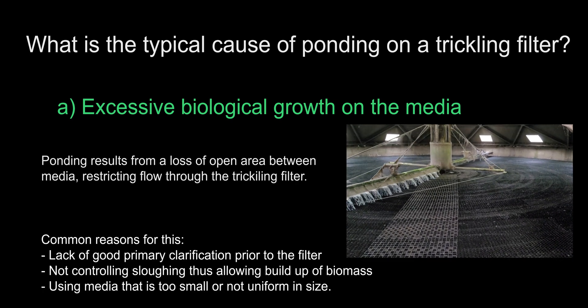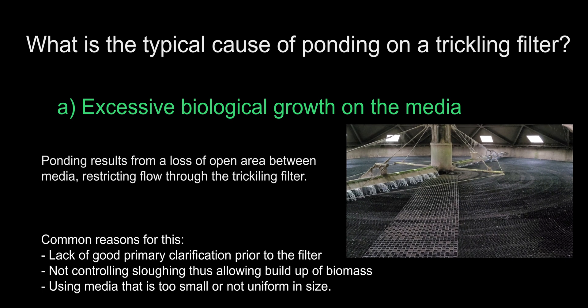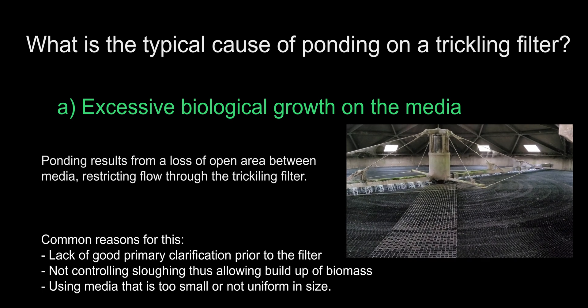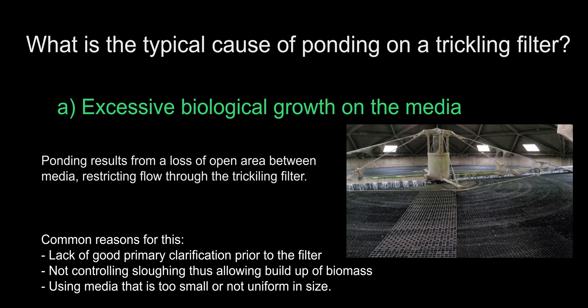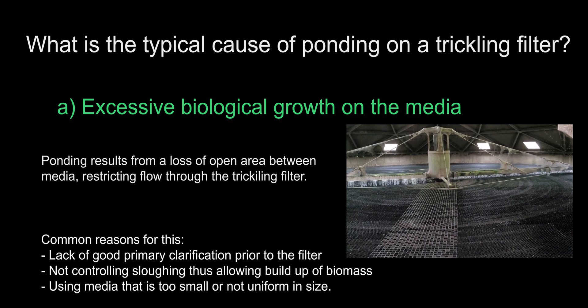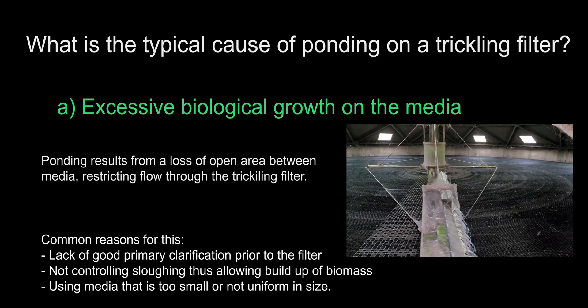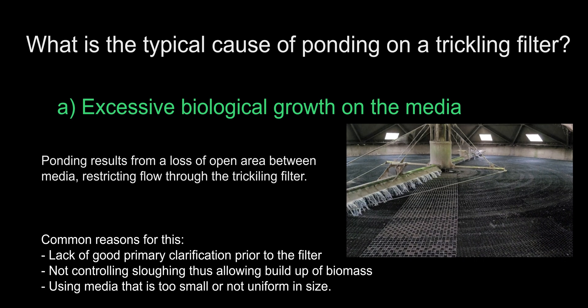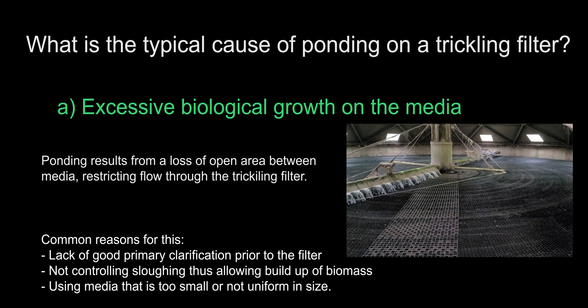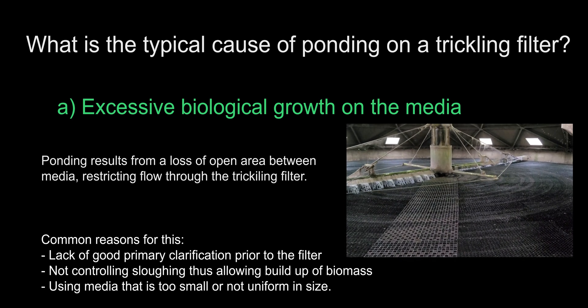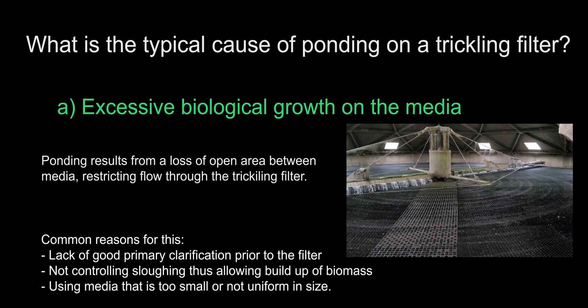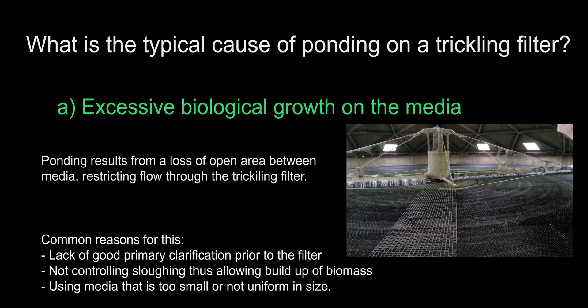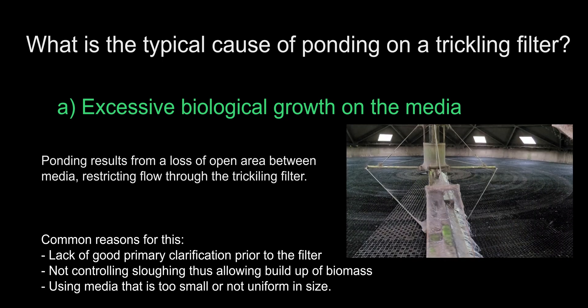Ponding occurs when influent can no longer pass through the filter media. The video displayed is of a working trickling filter, but as you can imagine, if that water was not draining through, it would sit on top causing issues. It's important to avoid too much biomass from accumulating on the filter media. This can be avoided by increasing the recirculation pump rate and slowing down the arm going around the filter, promoting the sloughing of excess biomass.